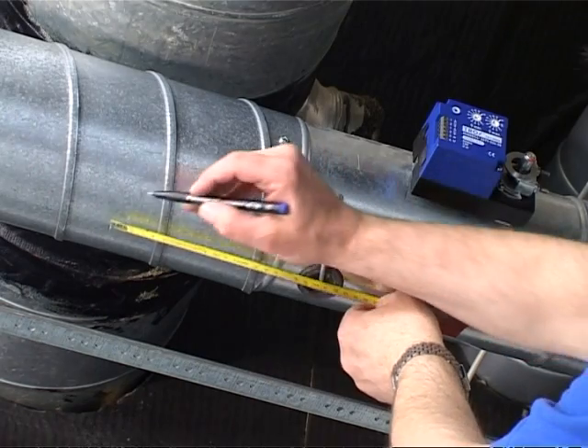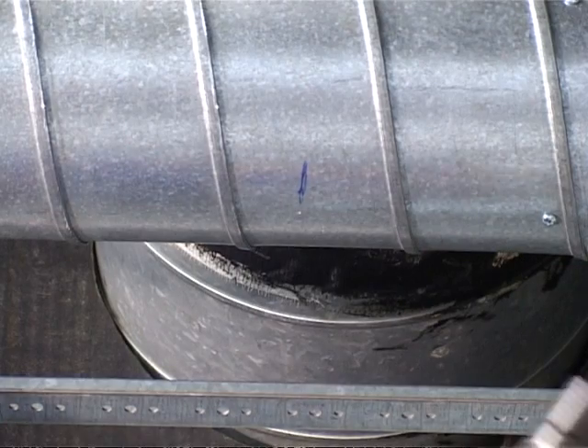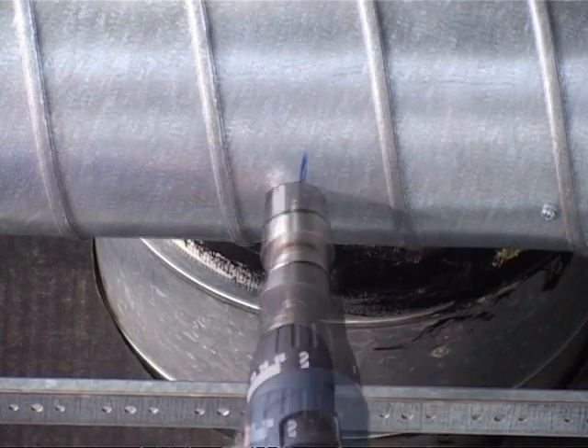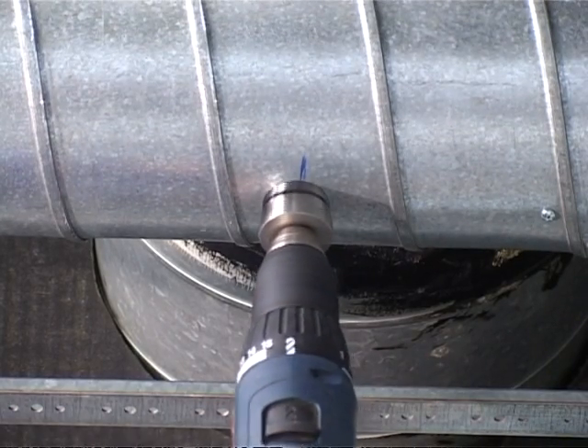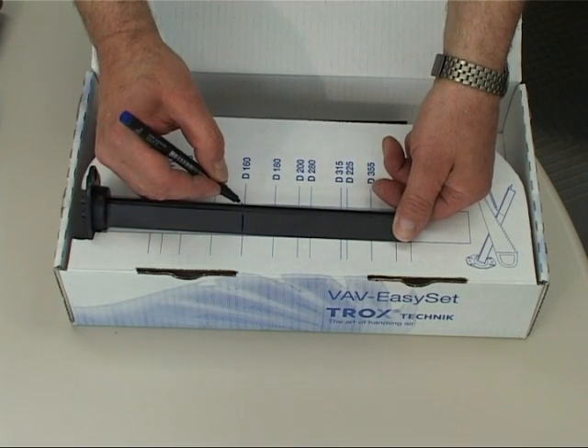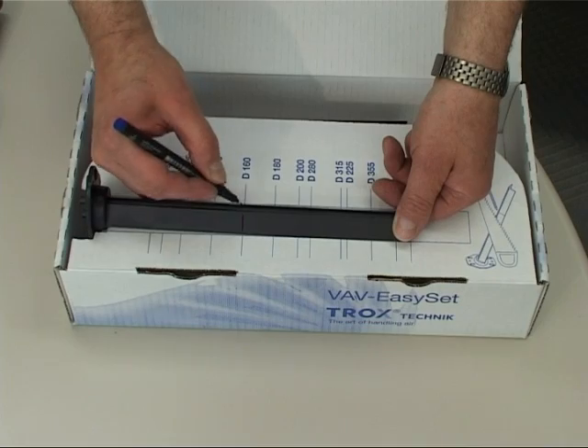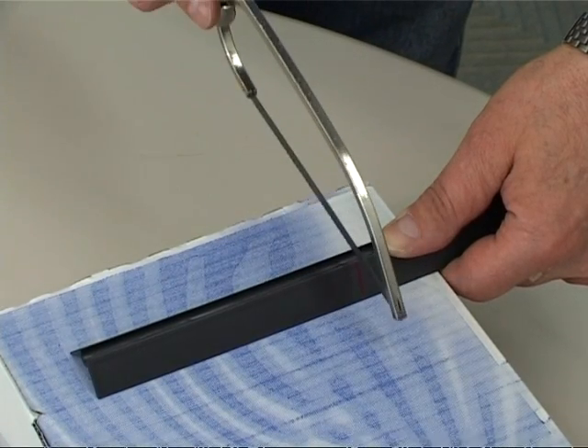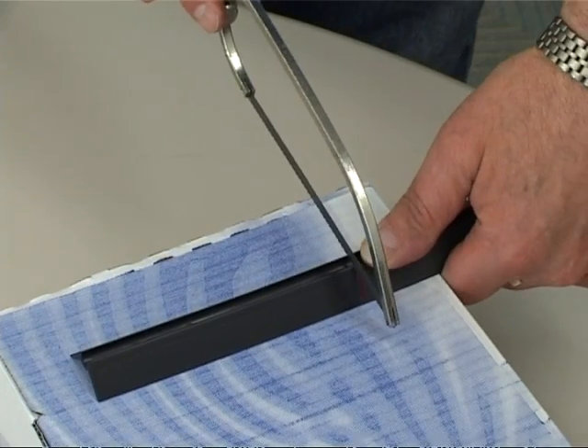For the installation of the differential pressure sensor, an opening with a diameter of 36 mm must be drilled rectangular to the control damper axle in the duct system. The sensor must be cut according to the diameter of the ductwork. A scale on the cardboard package of the EasySet assists to establish the correct length.